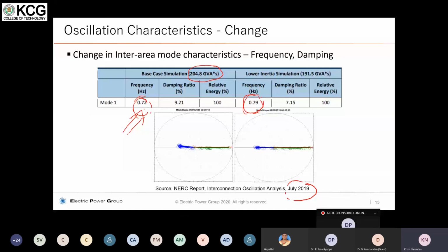It can be a multiple of 10 times or 20 times that of the actual disturbance. For example, if a 20 megawatt generator has a disturbance of 20 megawatts, this 20 megawatts will appear as 200 megawatts in the tie lines, basically. So this is the kind of danger that happens. That's why it's very important to monitor these things in real time, to see if there is a change in oscillation characteristics, to know the amount of change that has happened and what natural frequencies are disturbed. When you have a disturbance in your system, what is the forced response, which is very close to this natural response, that can cause inter-area resonance.